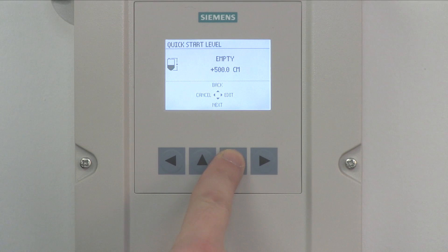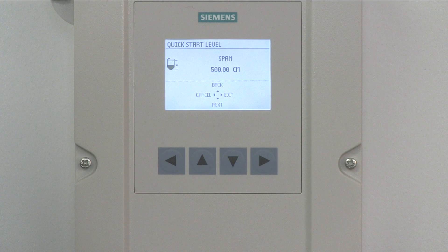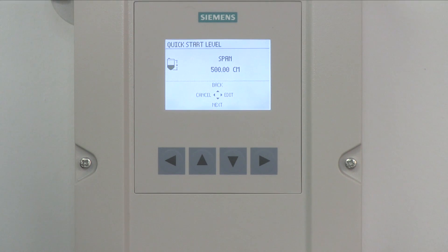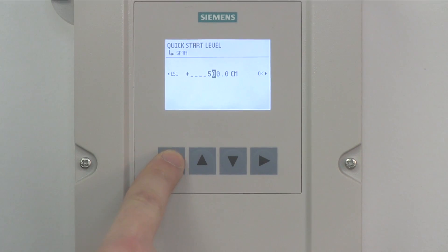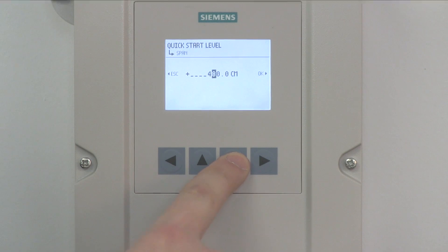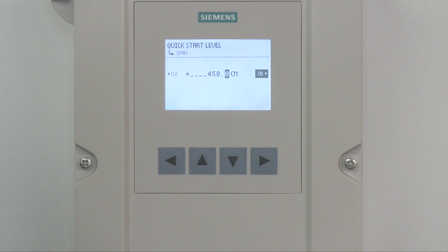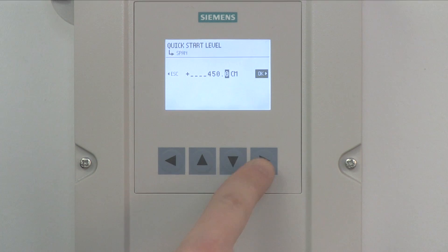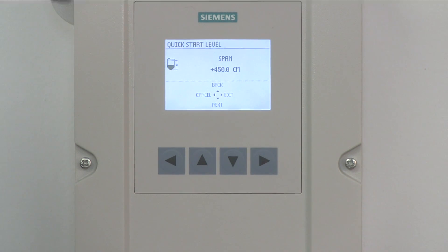Press the down arrow to select Next to proceed. The next step in the Quickstart Wizard is to enter the span distance. Press the right arrow to select Edit to enter the span distance. Use the left and right arrows to move the cursor. Use the up and down arrows to increase or decrease the span distance value. The span is the measurement range from the process empty point. Once the span distance value has been entered, press the right arrow until OK is highlighted and press the right arrow to select.